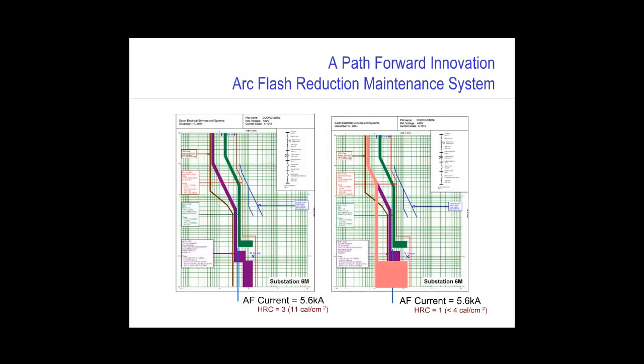It's important to note here that I may be sacrificing coordination with this setting. Difficult to see, but on the far left of both curves is a brown colored line showing the largest motor on this system and its starting curve. And as you can see, when I'm selectively coordinated on the left, I can start that motor into that feeder circuit breaker. But on the right, in the ARMS mode, you can see that if I tried to start that motor while I was set in the ARMS position, my feeder breaker would trip. So I've lost selective coordination. I'm effectively trading coordination for people safety. If someone's working in energized equipment downstream, it's probably a good trade.